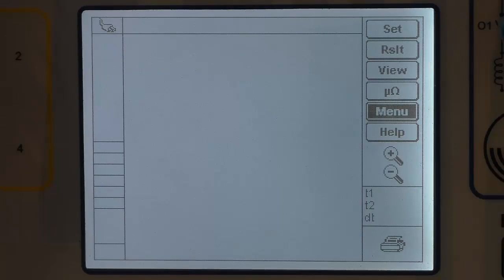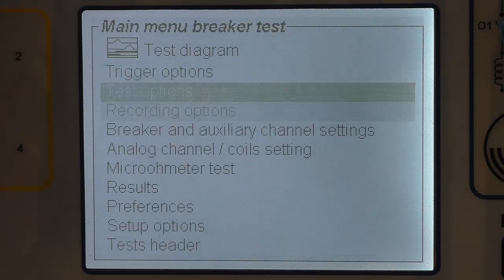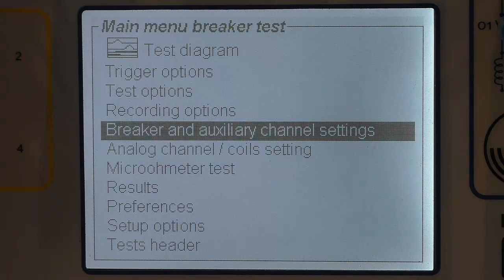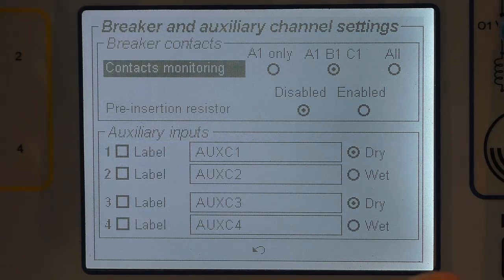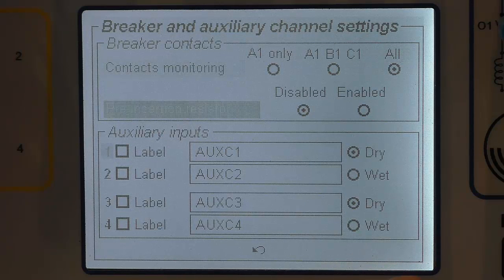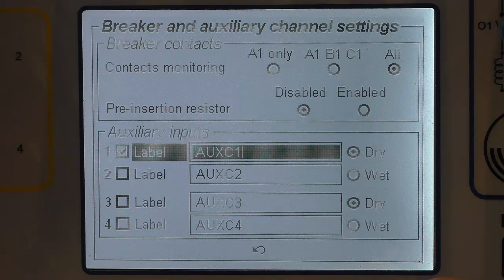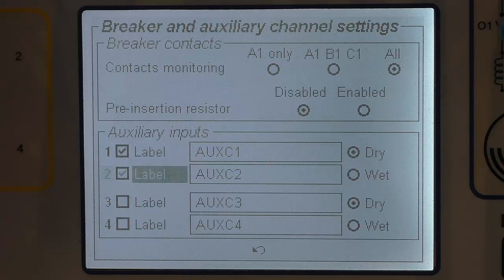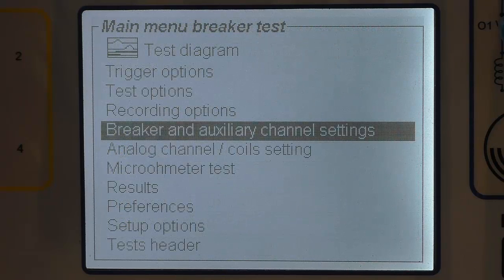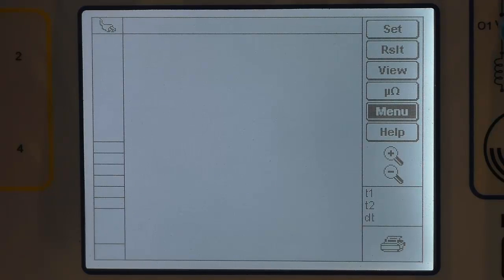By default, the secondary main contact is not active and the auxiliary contacts are not active. So we'll go into the menu by clicking the dial in order to set the auxiliary contact and the second main contact timing channel so that they appear on the trace. In order to set the main contact timing channel, we click on contacts monitoring and we select all, click the dial. We can then select each of the auxiliary contacts and name them if required. Second, third and the fourth. Once this is done, we can hit the return soft key, click the dial and get back to the test diagram ready to run the test.